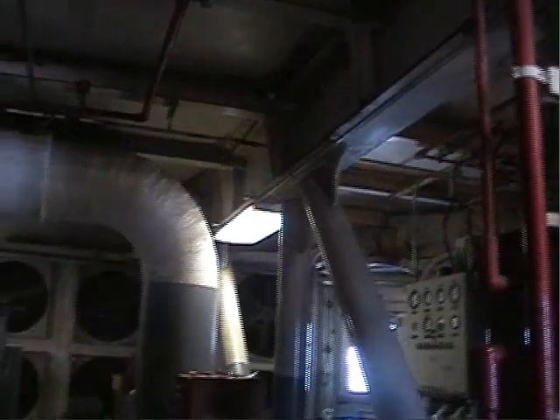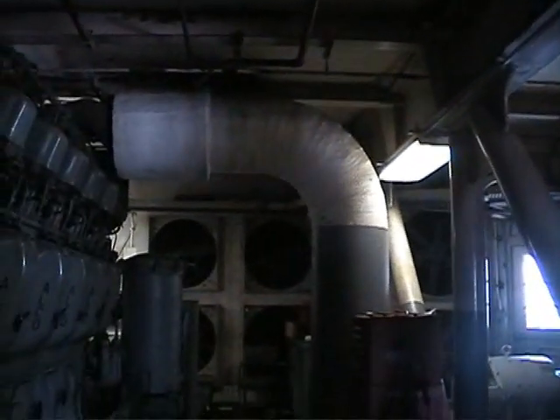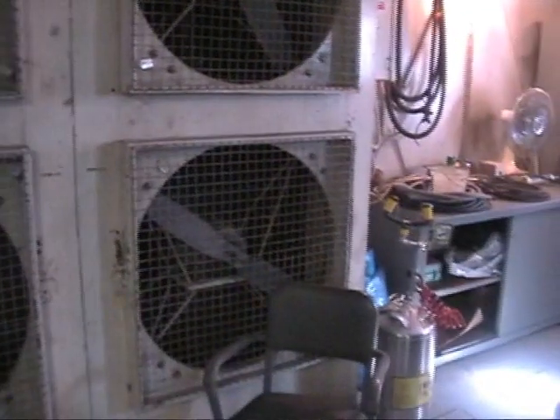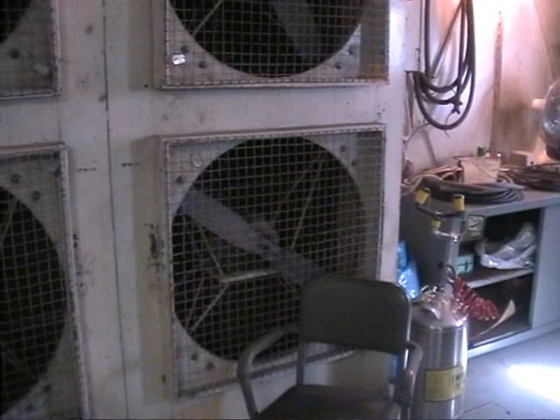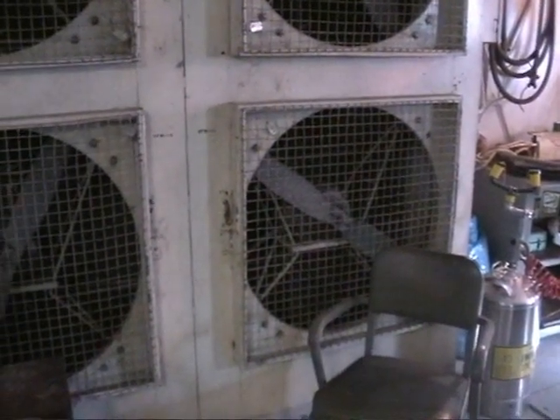This is part of the fire system — it's shut down right now. If it had been on and you made a flash, chances are we'd have set it off and dumped our power. Also, the motors are fine. We could change the fans out, double the airflow, and make it much quieter. They're running at about 90 dB level just with the fans running. By changing that out, that'll help reduce the total noise overflow in here.